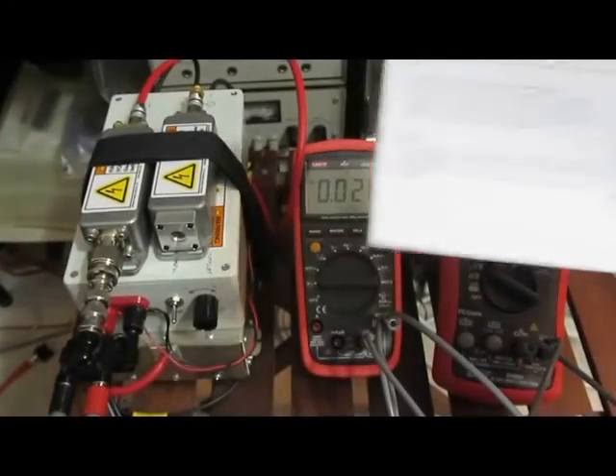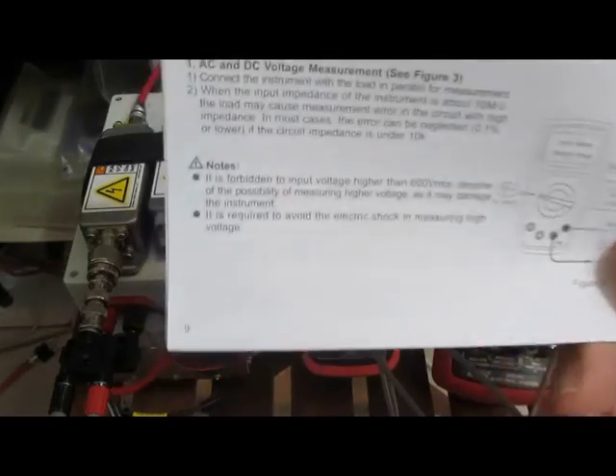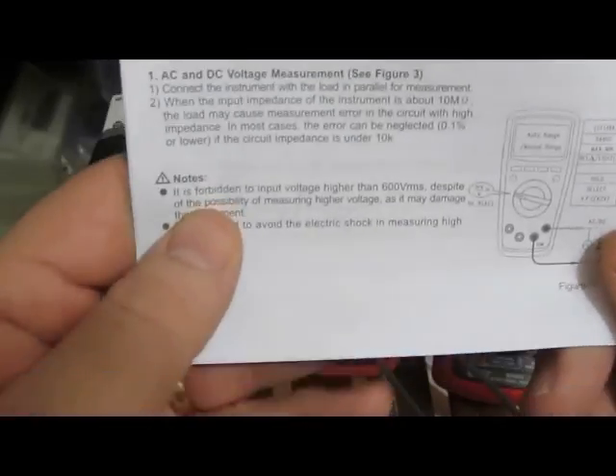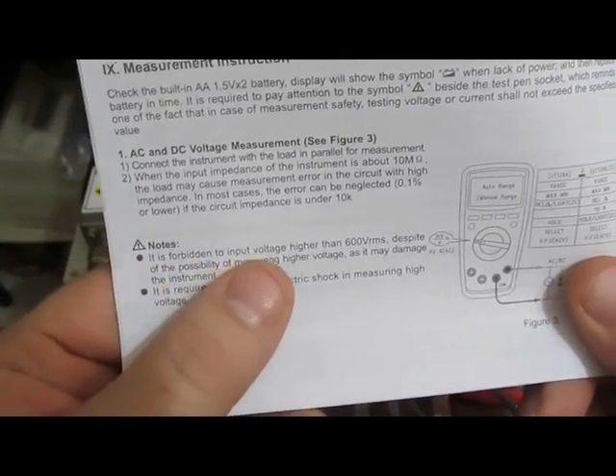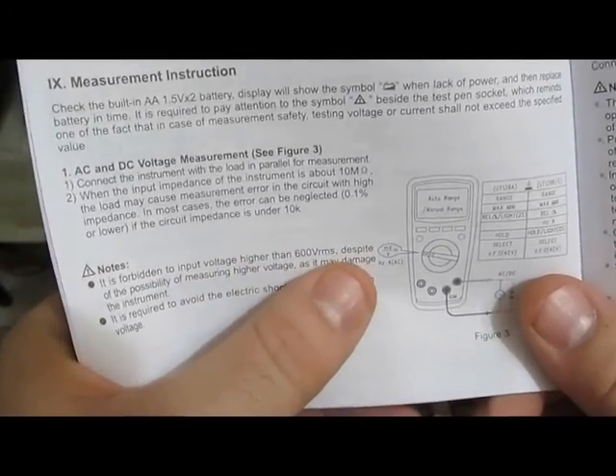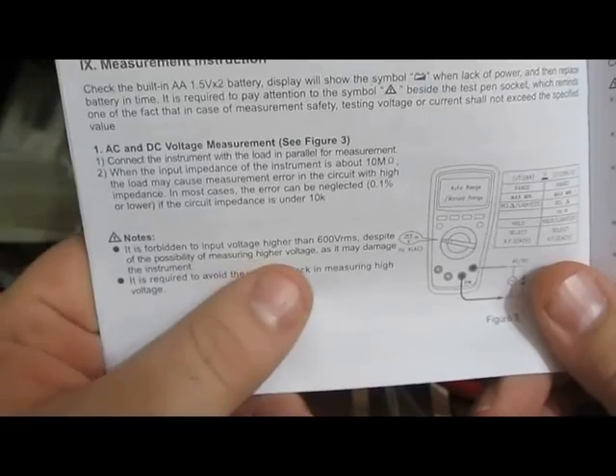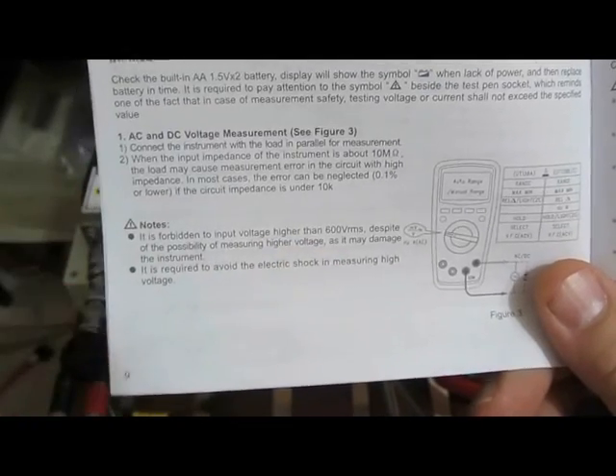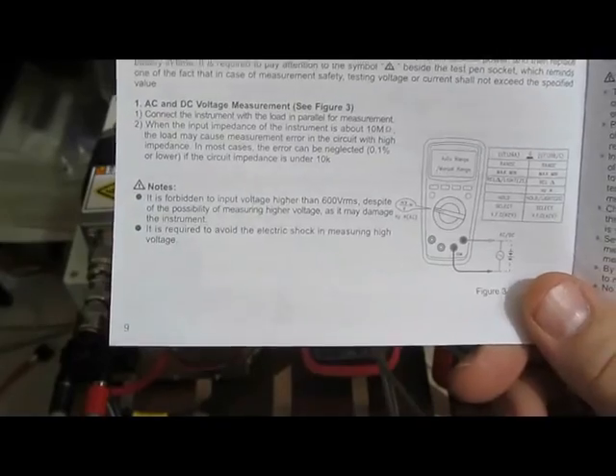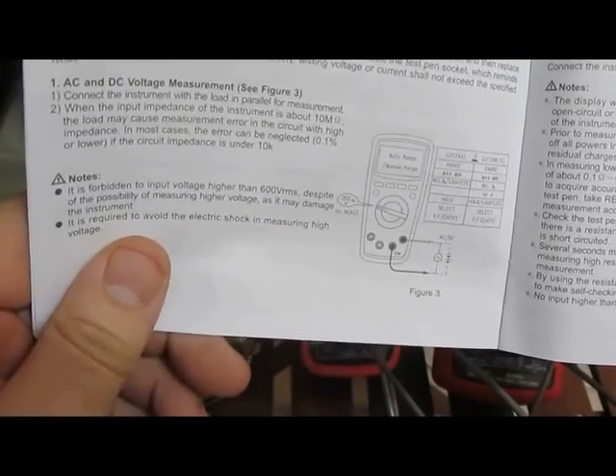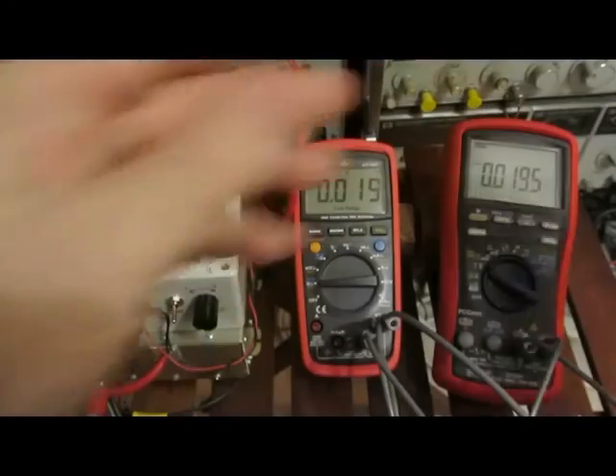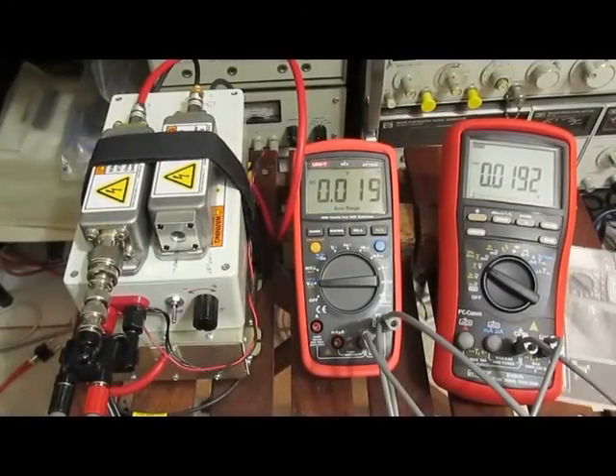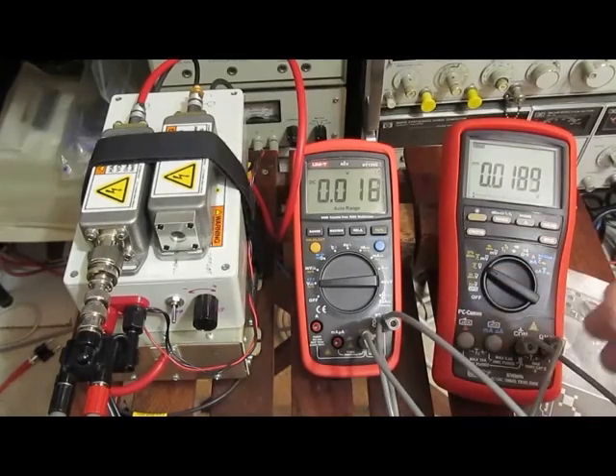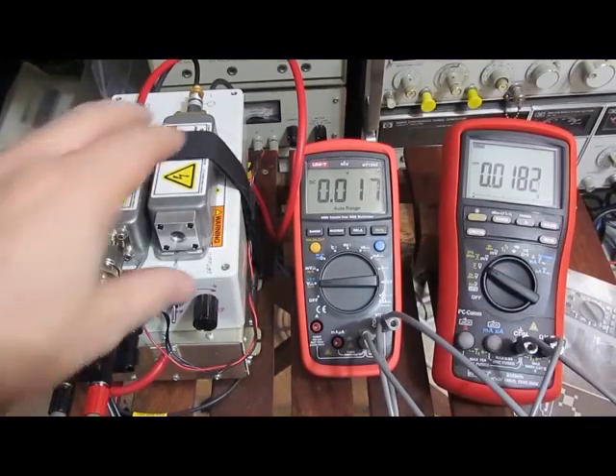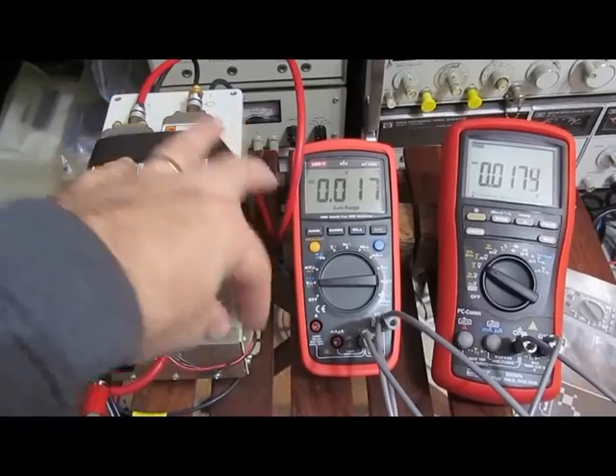This next test, you can see I've got out the high voltage supply. This is on page 9 of the manual. It says it's forbidden to input voltage higher than 600 volts RMS despite the possibility of measuring higher voltage, as it may damage the instrument. So I would say that's our upper limit, 600 volts. So I've got the Brymen out here to use as a reference. The 2 meters are just in parallel and attached to the output of the high voltage supply.